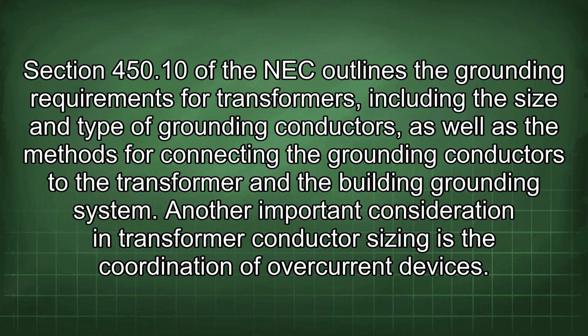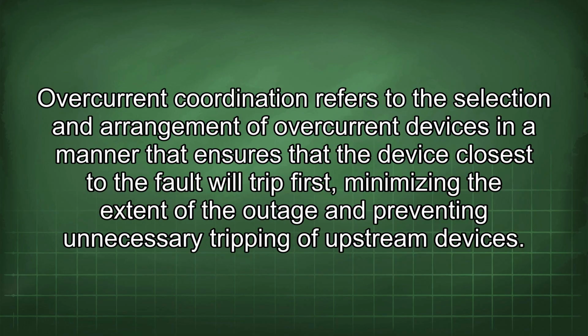Another important consideration in transformer conductor sizing is the coordination of overcurrent devices. Overcurrent coordination refers to the selection and arrangement of overcurrent devices in a manner that ensures that the device closest to the fault will trip first, minimizing the extent of the outage and preventing unnecessary tripping of upstream devices.